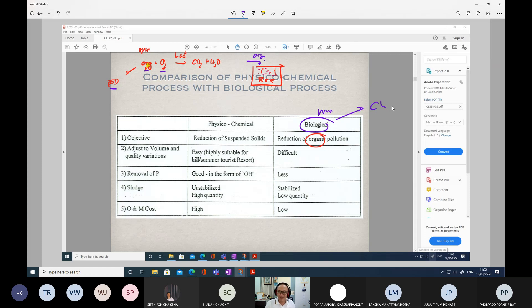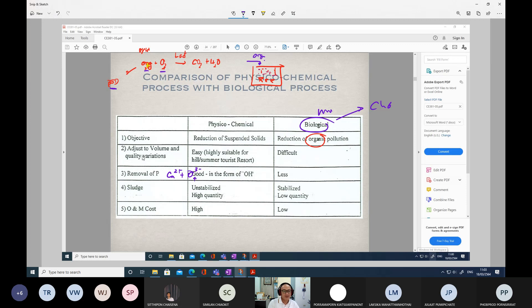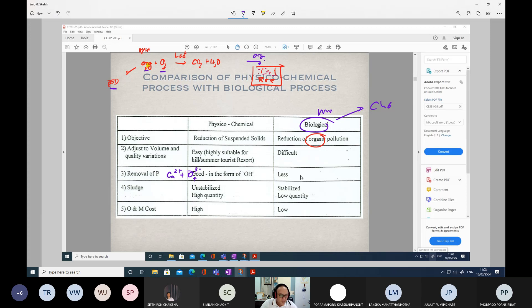Removal of phosphorus can most effectively occur using the chemical process — we add calcium to precipitate the phosphate. The most effective way to remove phosphorus is by applying the physical-chemical process. For biological processes, the efficiency is very low — we can say normally near zero percent removal for phosphorus by biological process alone.